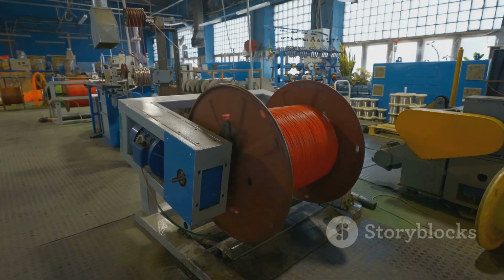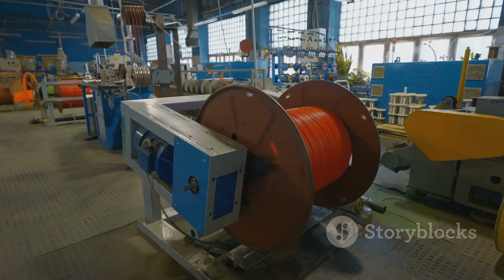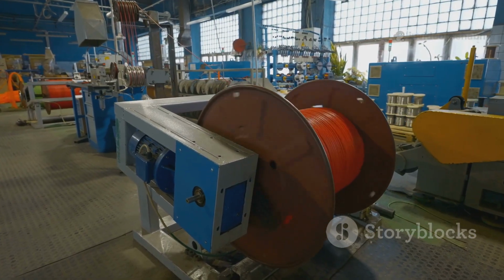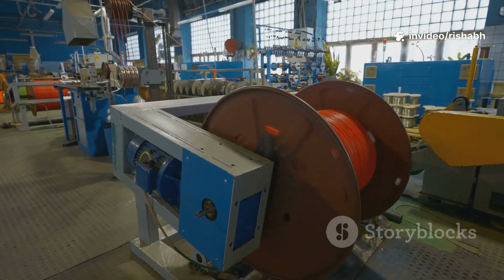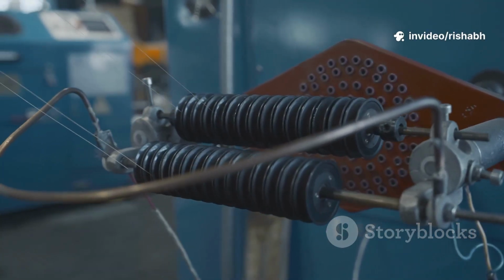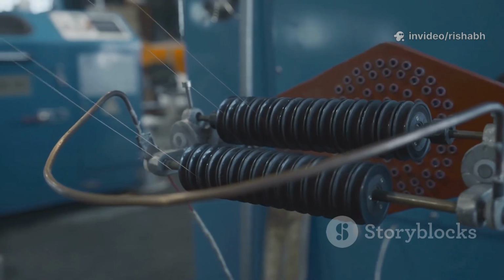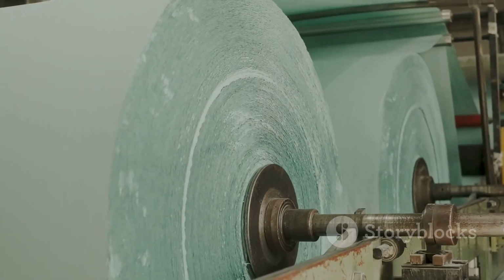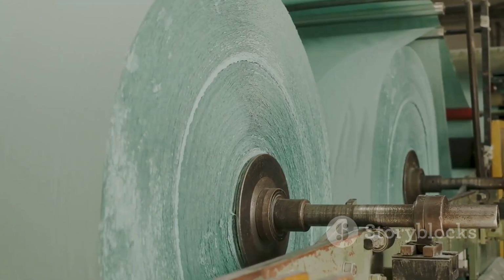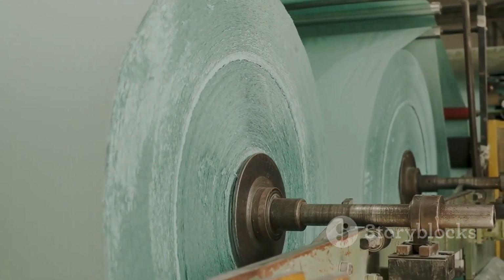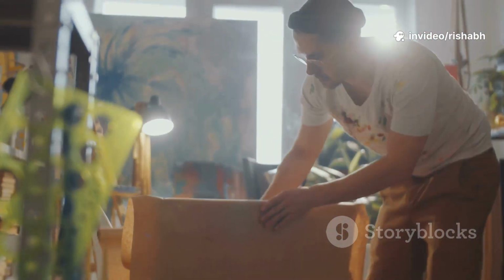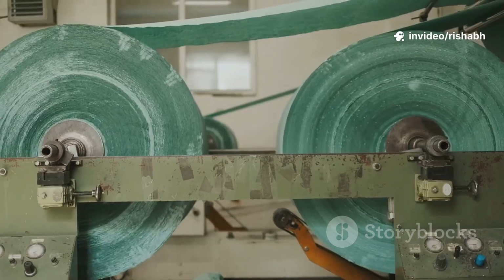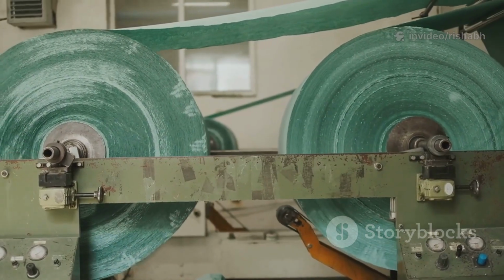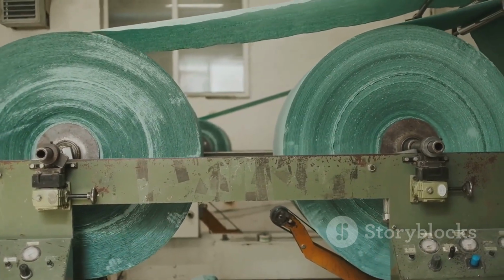The windings conductors themselves are not bare metal. Each strand is coated with an enamel or wrapped in paper insulation. These individual strands are then wound together to form the complete coil. The primary insulation material used in oil-filled transformers is a special kind of paper, often called kraft paper. This paper, derived from wood pulp, has excellent dielectric strength when impregnated with transformer oil.